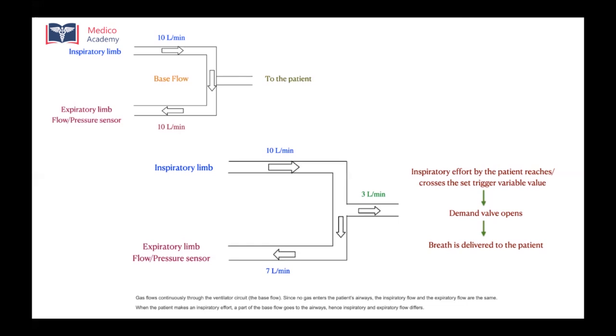Also, you need to see that you don't keep very low trigger values. Suppose you keep trigger values at 1 liter per minute. When the patient just moves his head from this side to that side, the ventilator will sense it as a movement which causes very small flows like 1 liter per minute, and the ventilator will start giving mechanical breaths. That can result in hyperventilation of the patient, which is also not right. So that is why you need to know that a trigger value of 3 to 5 liters per minute in a flow-triggered, or -3 to -5 centimeters of water in a pressure-triggered ventilator, is important. Okay, so that's about trigger.